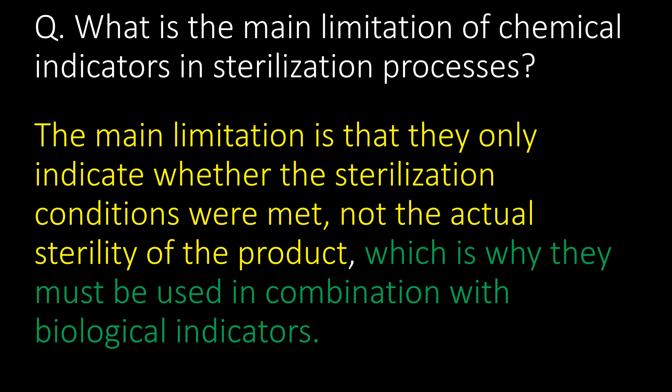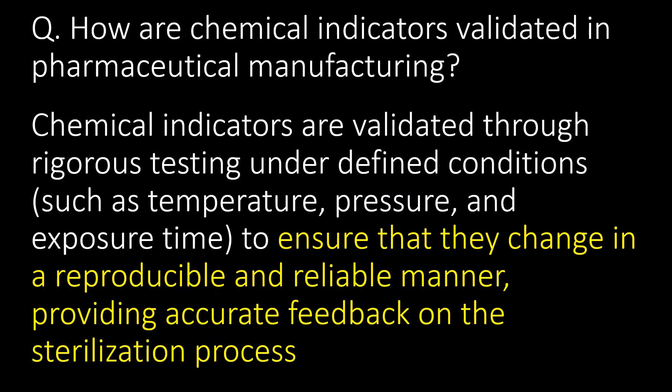What is the main limitation of chemical indicators in sterilization processes? The main limitation is that they only indicate whether the sterilization conditions were met, not the actual sterility of the product, which is why they must be used in combination with biological indicators. How are chemical indicators validated in pharmaceutical manufacturing? Chemical indicators are validated through rigorous testing under defined conditions such as temperature, pressure, and exposure time to ensure that they change in a reproducible and reliable manner, providing accurate feedback on the sterilization process.